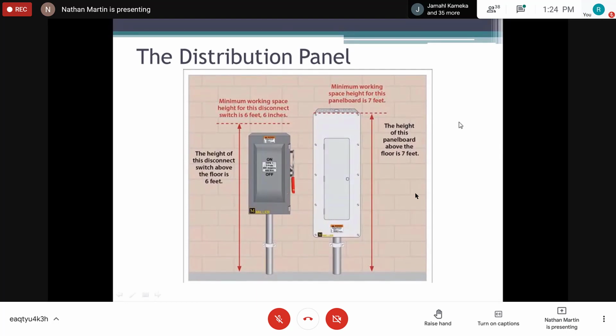So it's very critical when you are mounting panels. Also, it allows a person to easily disconnect supplies in case of an emergency. If you put it out of reach, they just can't reach it, and they have to go run for a ladder. In case of an emergency, they have to run for a stool. They have to go try to find a ladder to climb up to be able to disconnect. No, they should be comfortable to disconnect the breaker that is at the highest point, right? So they should be able to disconnect the breaker at the highest point.